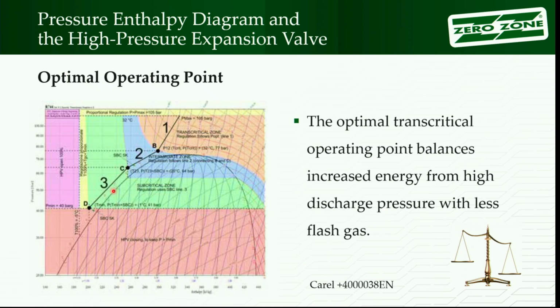When you're down in subcritical mode, that's a punched in number. Usually you're looking at having a minimal amount of subcooling, and that's a number you punch in. The software is not deciding that for you. If you want 3, 4, 5 degrees, typically is the number. And to get that subcooling, we're condensing, right? So we're getting liquid out of the condenser. To get that subcooling, it's going to close off that valve and back a little liquid up into the condenser. So when you back liquid up in the condenser, you might raise the pressure in the gas cooler as well. So that's all going to happen. That's going to kind of just move up, and it's going to control that.